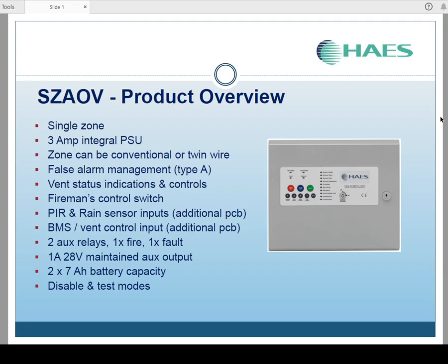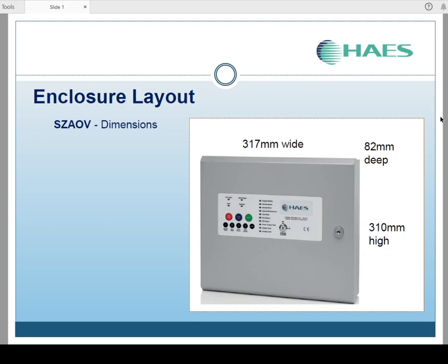vent control inputs using your 0 to 10 volt inputs from control equipment, again using the same additional plug-in PCB, two auxiliary relays, one fire and one fault, a 1 amp 28 volt maintained output suitable for magnetically held back windows, room for two 7 amp hour batteries, and disable and test mode functions. The panel's overall dimensions are 317 wide, 82 millimeters deep, and 310 millimeters high. The back box is obviously slightly smaller than the door on the front there. Details can be found in our manual.